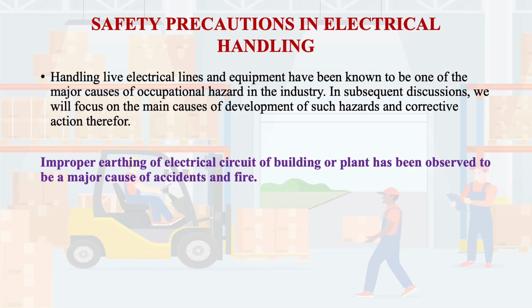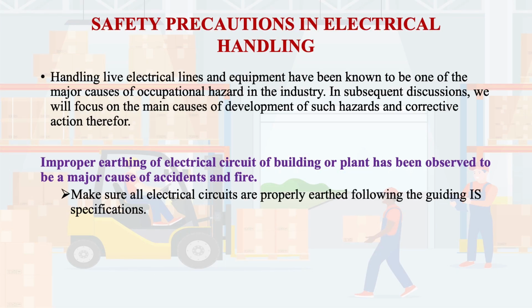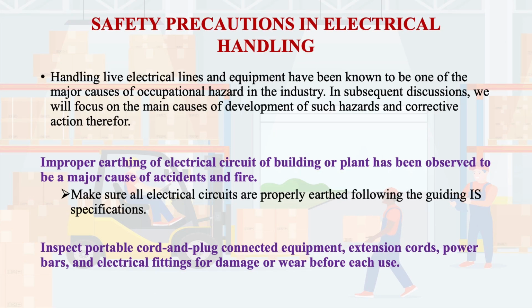Improper earthing of electrical circuits of a building or plant has been observed to be a major cause of accident and fire. What you can do is make sure all the electrical circuits are properly earthed, following the guiding IS specifications. Another thing observed in the industry is that if you inspect portable cord and plug connected equipment, extension cords, power bars and electrical fittings for damage or wear before each use, we can avoid unwanted incidents.